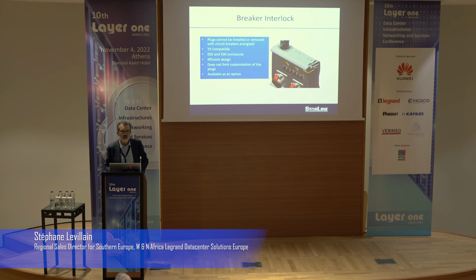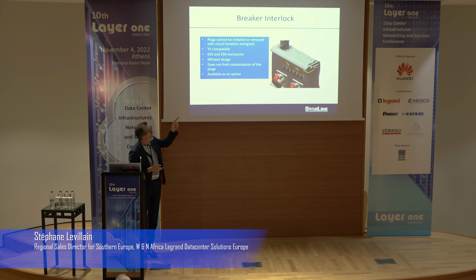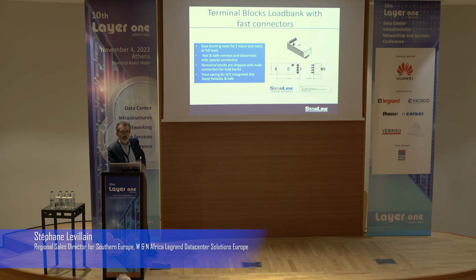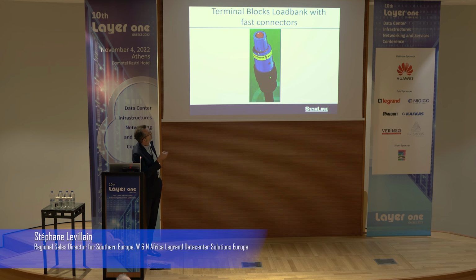In terms of different options, we could have some breaker interlock to avoid people inserting the tap-off while switched on. It needs to be switched off, and we have the metallic part to force the system to be switched off before inserting it. And when it comes to the terminal block load banks, we use fast connectors. You can see all the fast connectors. A fast connector is this kind of piece. When you want to test a full run of racks, you have your terminal blocks overhead, the cable, the fast connector, and then you make the running test. Then you can make the opposite, go to the other one, and so on and so forth. So it's very fast, very reliable, of course, because if you have to use wrenches, after 2 times it could be dangerous for the people, of course.